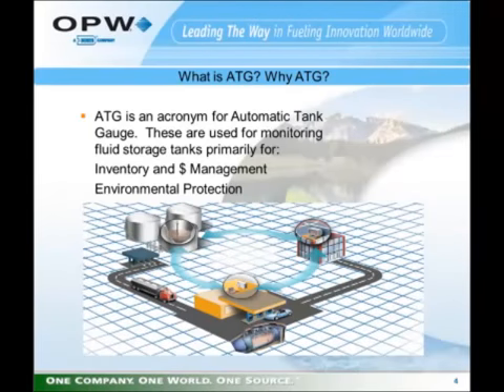ATG is an industry acronym for automatic tank gauge. Automatic tank gauges monitor fluid storage tanks primarily for inventory control and money management. The second important function they perform is environmental protection. They are used to monitor storage tanks, whether underground or above ground, and they can also be used to monitor fluid lines, piping, and sump areas where loose product might accumulate if a leak were to occur.